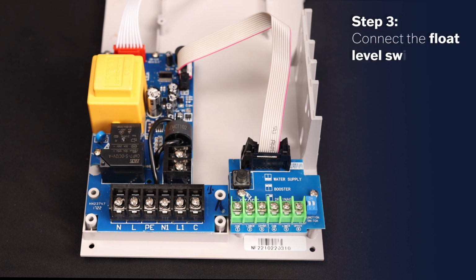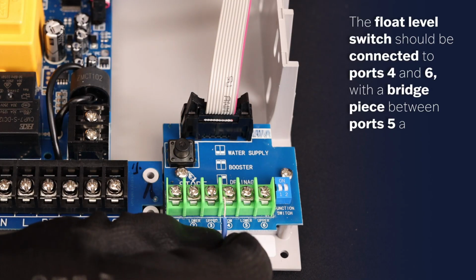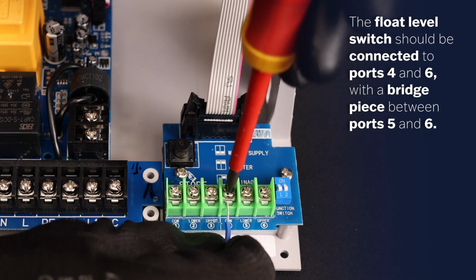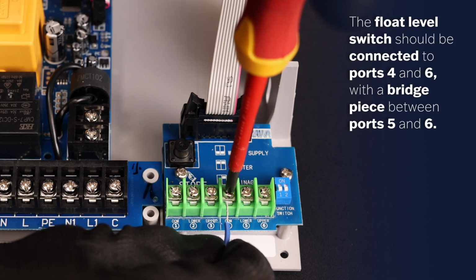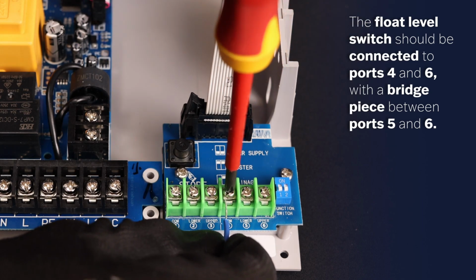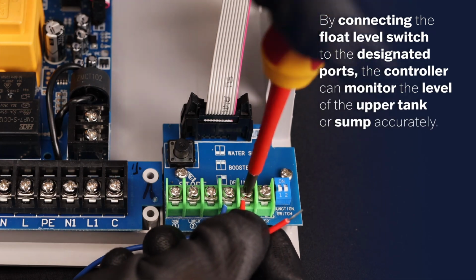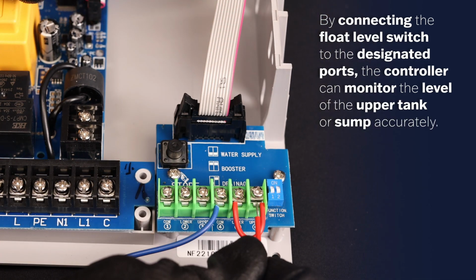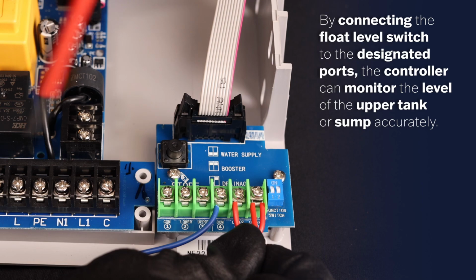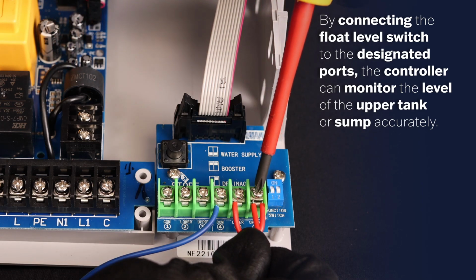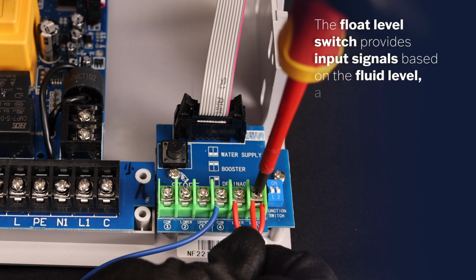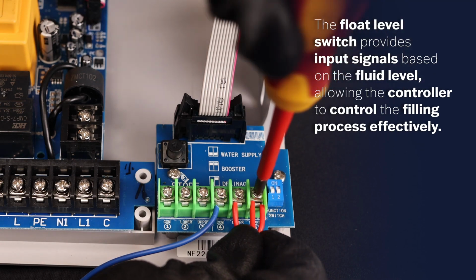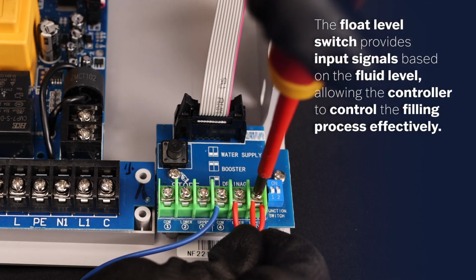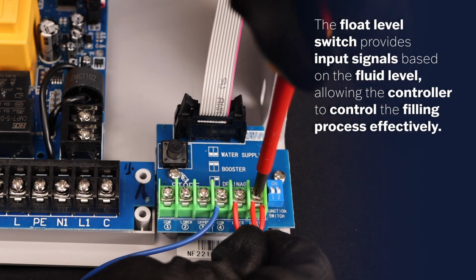effectively. Step 3. Connect the float level switch for the upper level tank or sump. The float level switch should be connected to ports 4 and 6, with a bridge piece between ports 5 and 6. By connecting the float level switch to the designated ports, the controller can monitor the level of the upper tank or sump accurately. The float level switch provides input signals based on the fluid level, allowing the controller to control the filling process effectively.